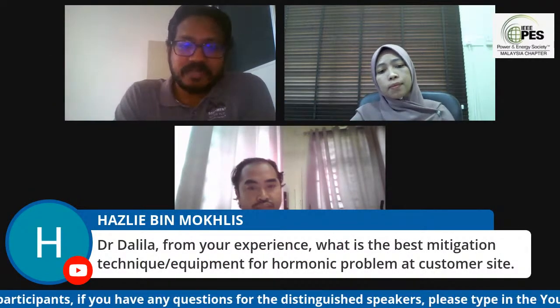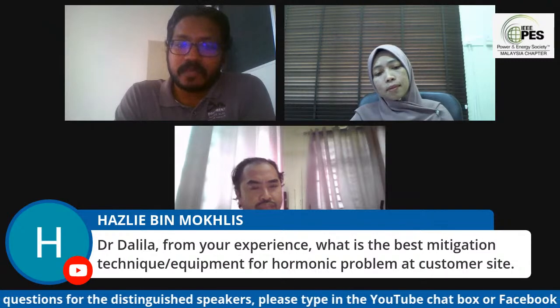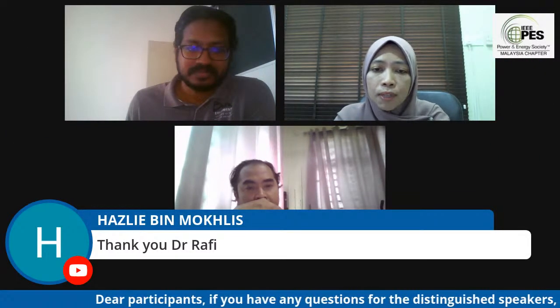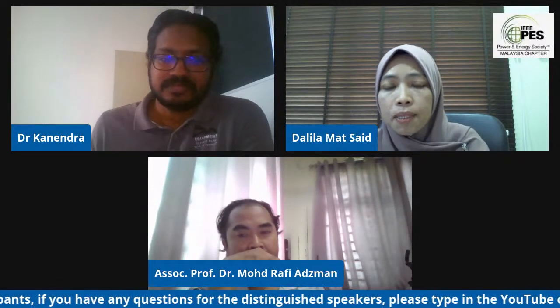The next question, please, from Prof. Hazli. Dr. Dalila, from your experience, what is the best mitigation technique or equipment for harmonic problem at customer side? Okay, thank you, Prof. Hazli, for the question. Usually, in order to mitigate harmonics, most of the industrial users choose an active filter, even though an active filter has an expensive cost compared to the passive filter, because it also avoids the resonance problem in the system. But it also needs detailed investigation. I cannot say this is the best, but it depends on the cause of the problem. In this situation, they choose the inductive filter. Okay, thank you.